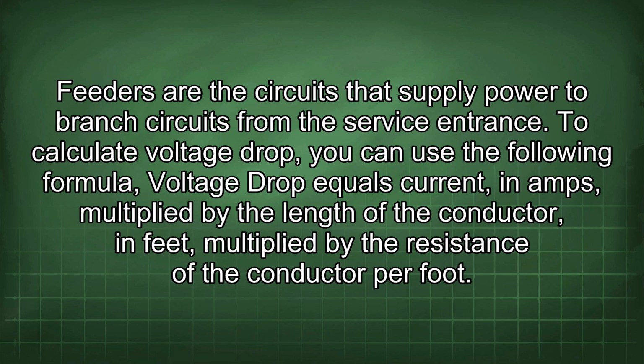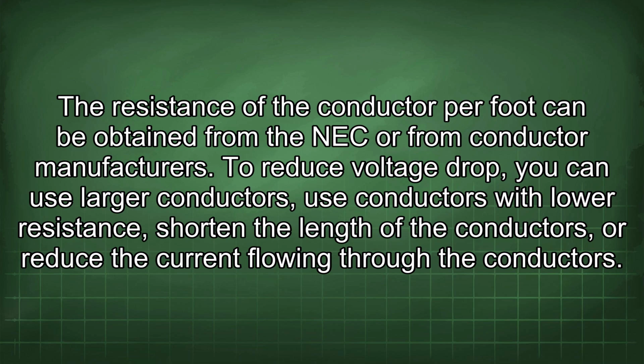To calculate voltage drop, you can use the following formula: voltage drop equals current in amps multiplied by the length of the conductor in feet multiplied by the resistance of the conductor per foot. The resistance of the conductor per foot can be obtained from the NEC or from conductor manufacturers. To reduce voltage drop, you can use larger conductors, use conductors with lower resistance, shorten the length of the conductors, or reduce the current flowing through the conductors.